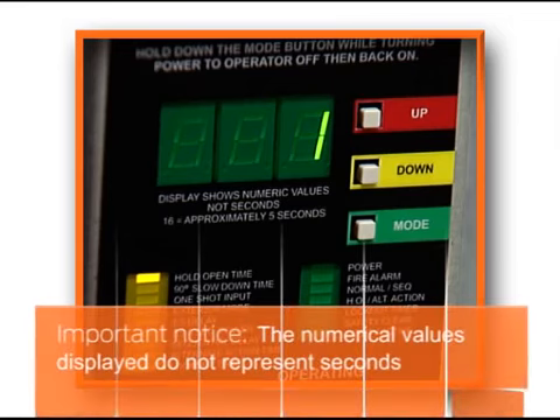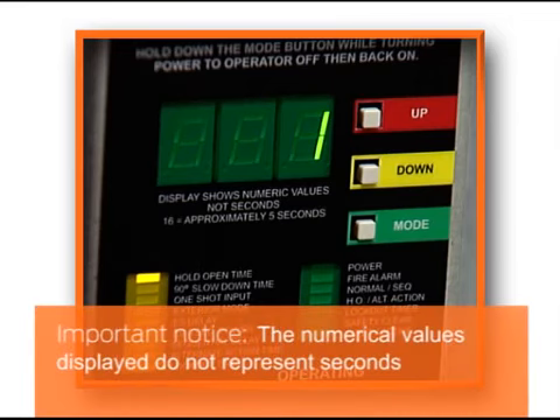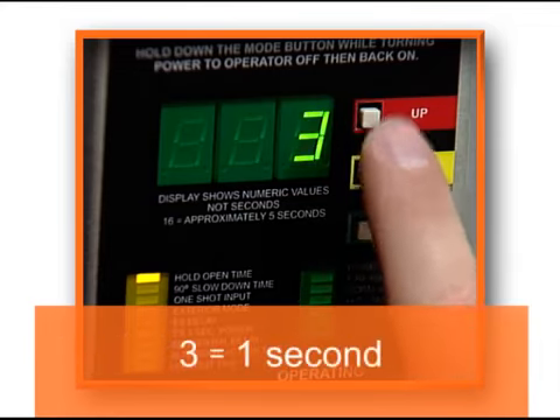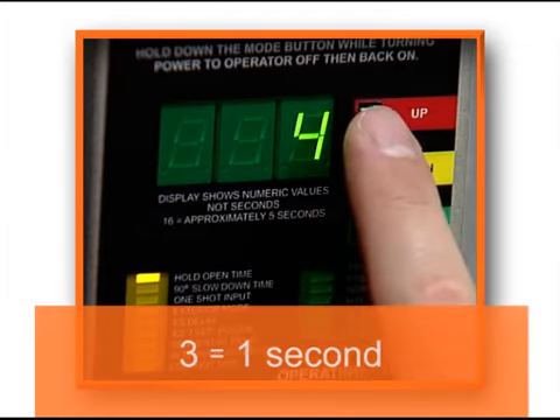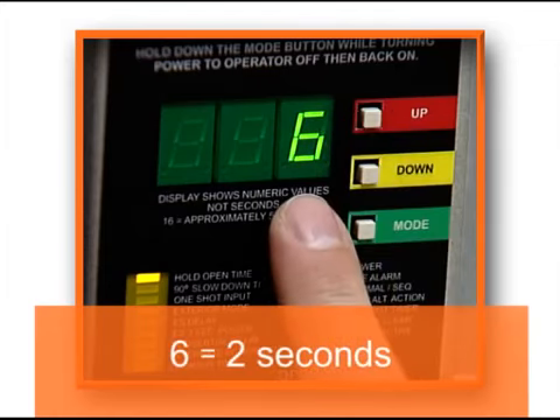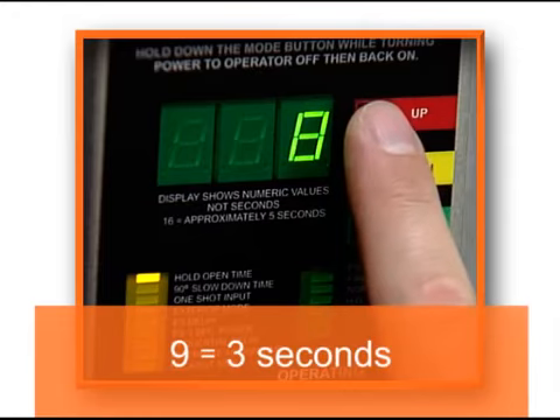It is critical to note here that the numeric values displayed do not represent seconds. The number 1 equals about 1/3 of a second. Therefore, a numeric display of 3 equals 1 second, a display of 6 equals 2 seconds, a display of 9 equals 3 seconds, and so on.